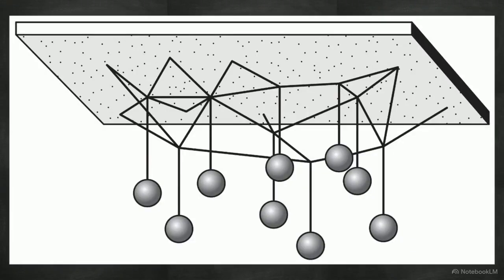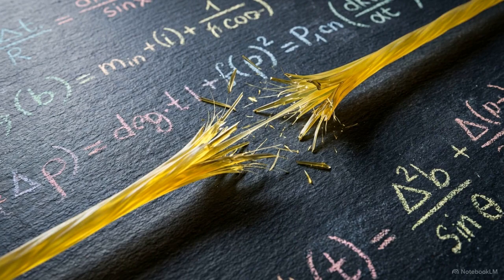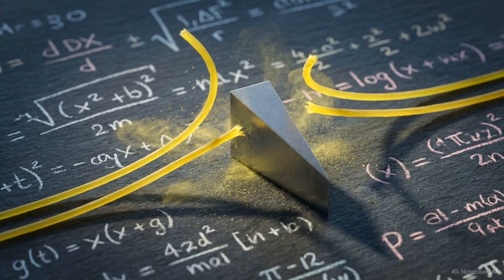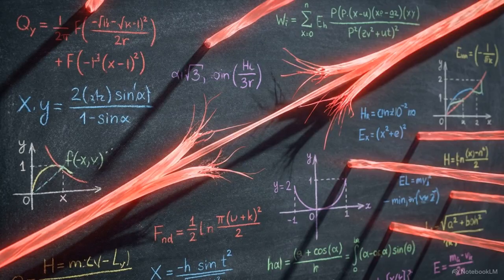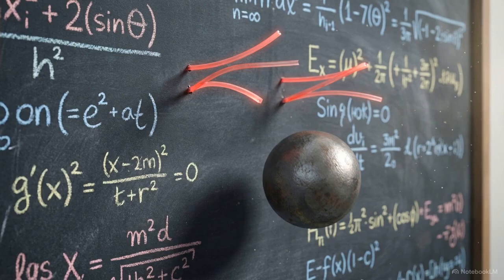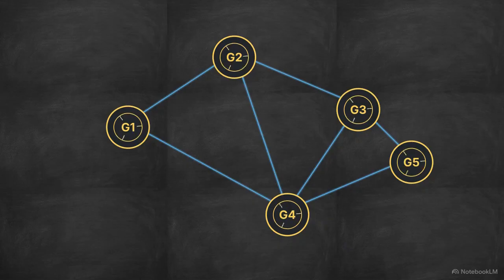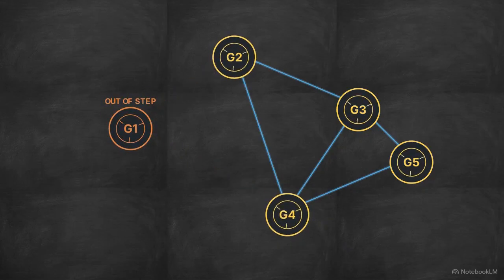In Elgerd's analogy, synchronous generators are heavy weights, and transmission lines are elastic strings holding the network in tension. Routine load changes act like minor vibrations. The strings stretch slightly, but the weights eventually settle back into place. This is small signal stability. Transient stability involves a massive, catastrophic shock. A transmission line fault acts as a blade slicing through one of the primary elastic strings holding the network together. When a string is cut, the surviving lines must instantly stretch to absorb the massive shift in tension and fluctuating force. If the remaining lines cannot absorb the weight, they snap, and the mass falls entirely. In a power system, this physical drop represents a generator losing synchronism and being ejected from the grid.